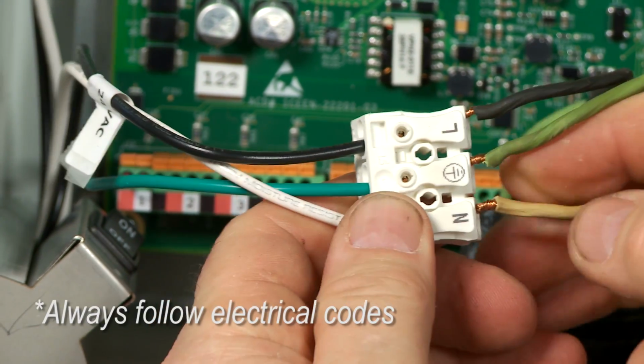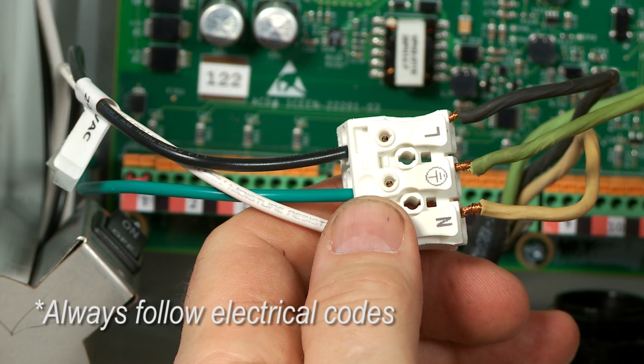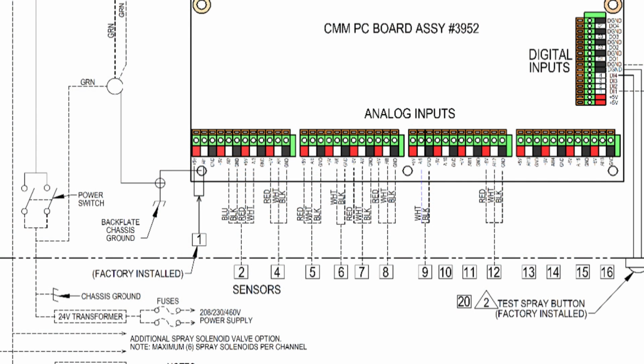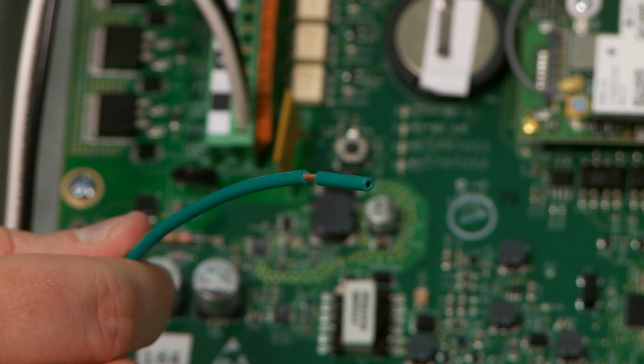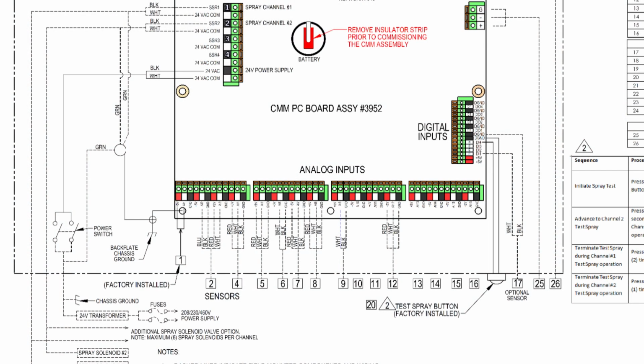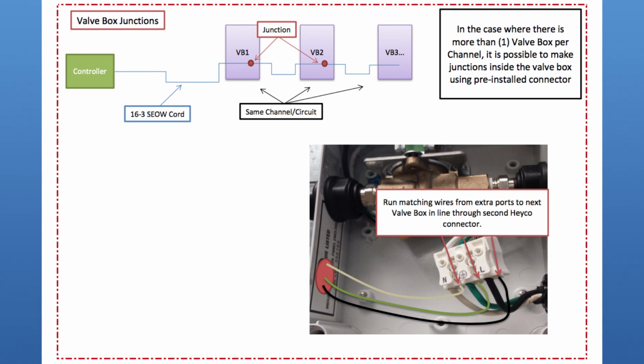In order to prevent the possibility of a ground potential difference in the 24-volt system, you need to ensure that all Evaporcool electrical items share the same ground as is used in the main control cabinet of the unit being installed upon. To ensure this is the case, a green ground cable must be run from the cabinet ground or main panel ground to the Evaporcool 24-volt transformer. From there, the ground cable will continue to be run to the controller with the controller power cables.